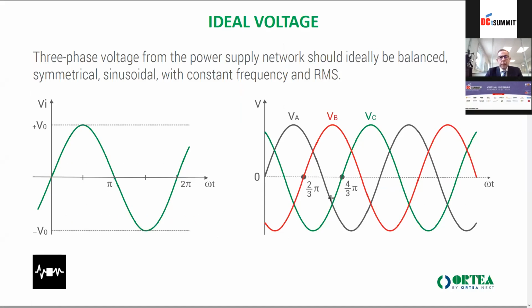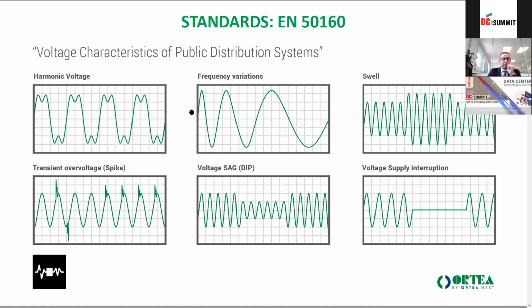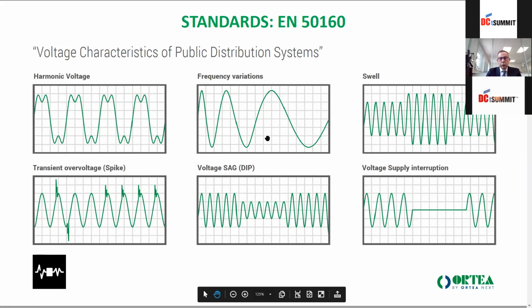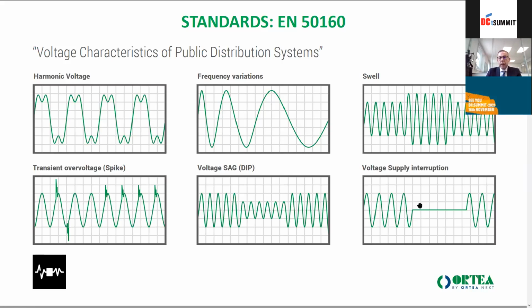The problem is that this is not always the same, because many times you have harmonics, you have frequency variation, you have swells, you have sags, you have transient spikes, and you have sometimes a voltage interruption. So each problem of these does have a solution, like a frequency converter to solve the problem of the frequency. Sags and swells can be solved by sag compensator, supply interruption by UPS. So we may face during the execution of our industrial or service process different problems, but we can have also different solutions.